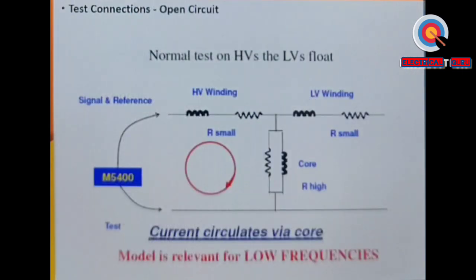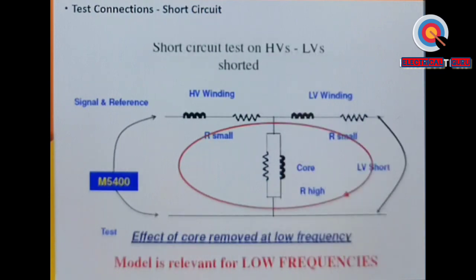So this circuit diagram shows the open circuit test. Here you can see on the LV side, this is an infinity impedance. So the current has to circulate in this area only. This will be possible only through the core. So at a low frequency, this will identify the problem in the core area. In the short circuit test, since the LV side is short circuited, the impedance of the core is relatively higher. So the core is not involved in the process, and then the winding is involved, and that's how it can identify the winding deficiencies.